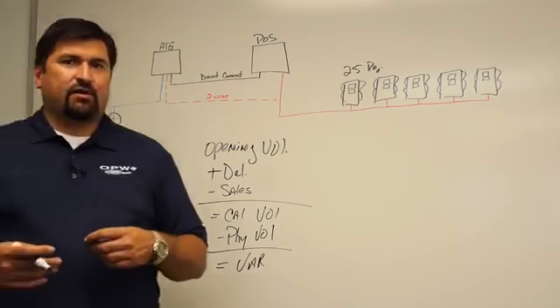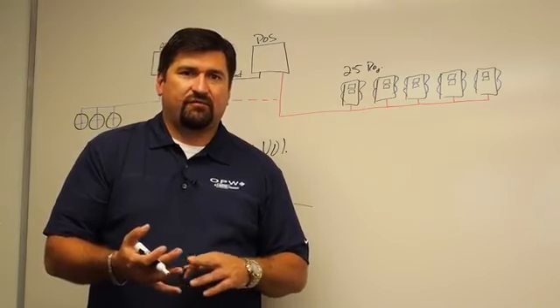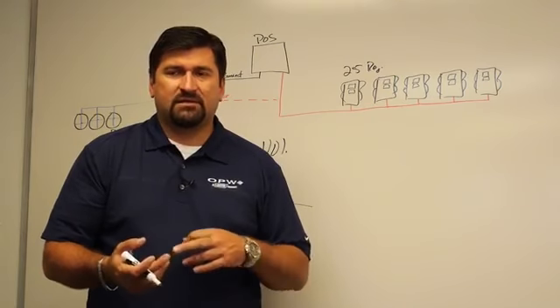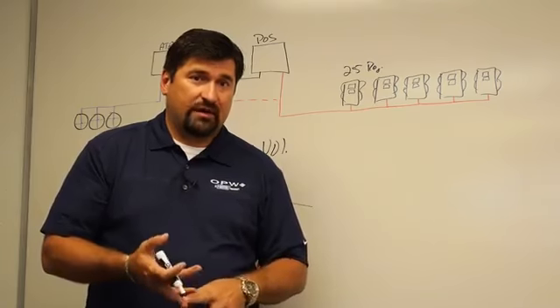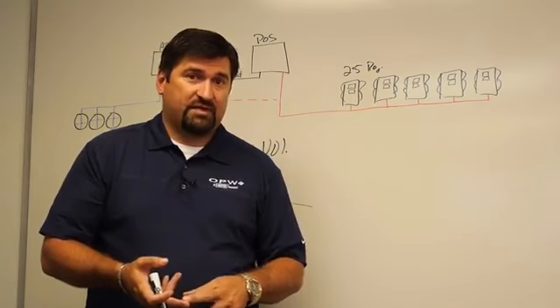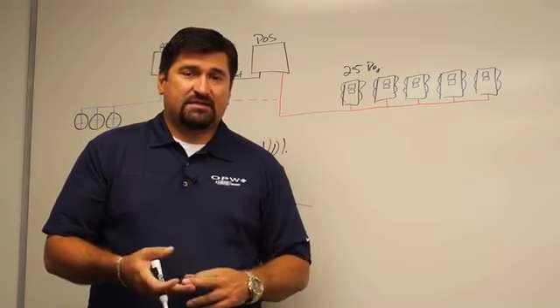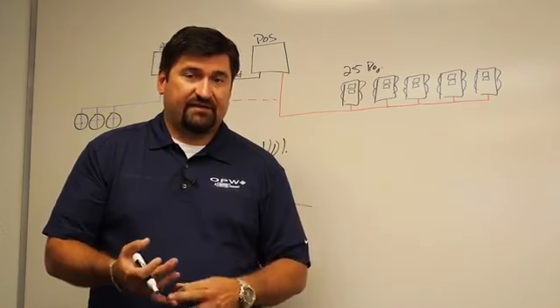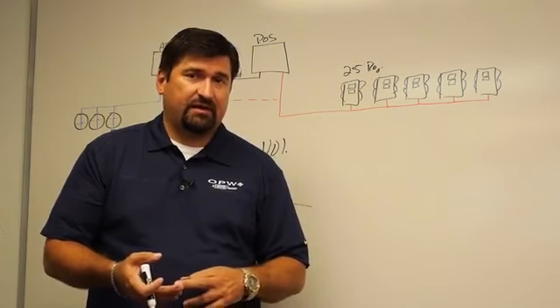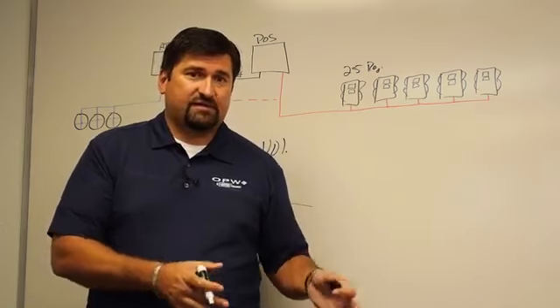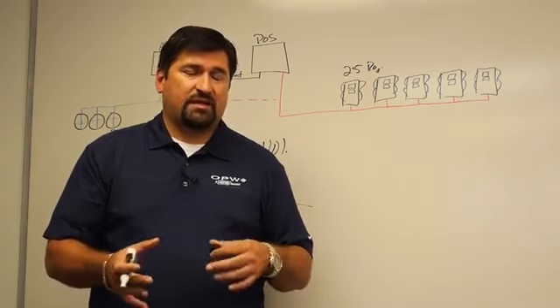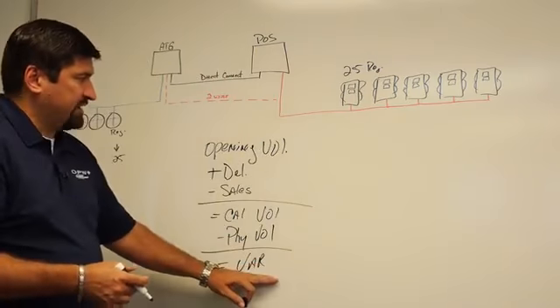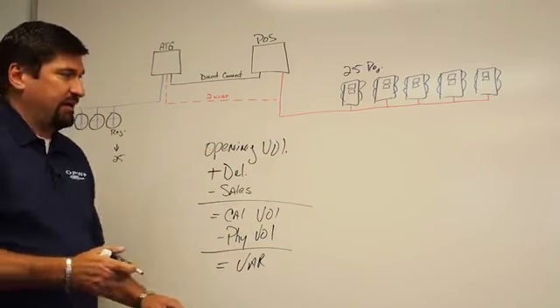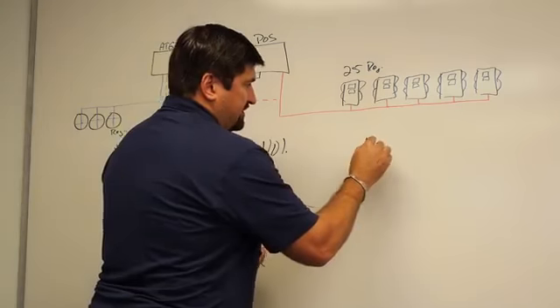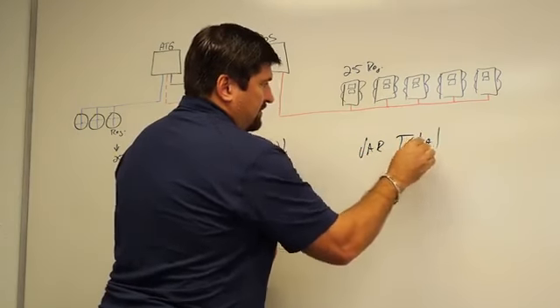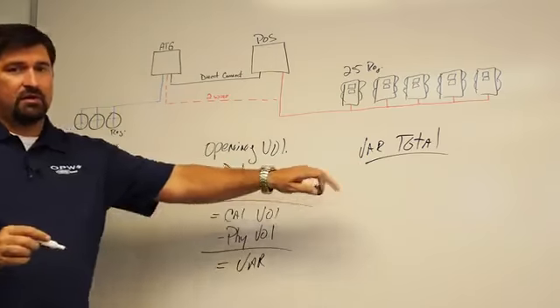When you start looking at your percentages, you're looking at either 1% of throughput plus or minus 130 gallons, but some municipalities and some local regulatory requirements are 0.5% of throughput or delivery. You can reconcile over a 7-day, 10-day, 15-day, or 30-day period. These could be fixed periods or rolling periods, so it just depends on the state as to what the variance is. Then it adds this up for that period, and it gives you your variance total. And this is what people are looking for.